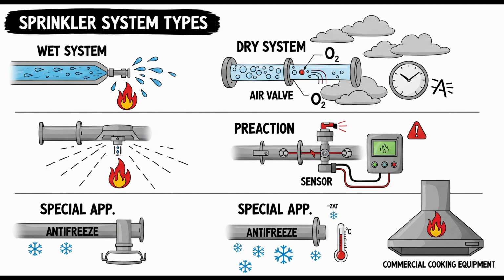Essentially, yes. Now, about using nitrogen specifically, you mentioned it can be used instead of air. The source talks about using it for an increased C value in hydraulic calculations. What's that about? Yes, this is a more advanced application. Nitrogen, being an inert gas, doesn't support oxidation, so it helps prevent or significantly reduce internal corrosion inside the steel pipes of a dry system. Okay, less rust inside the pipe.